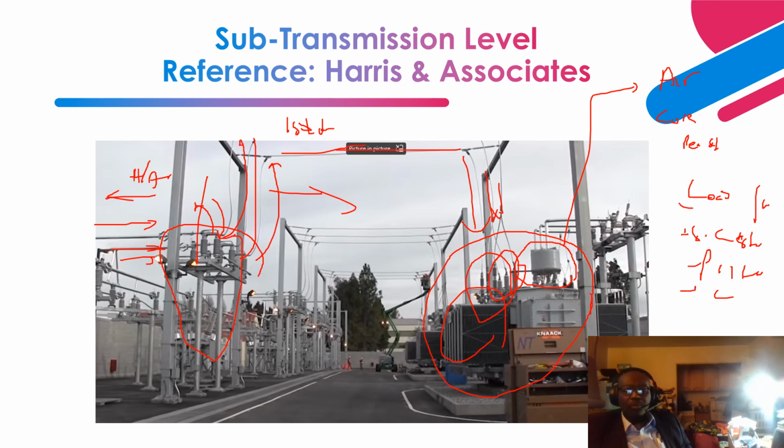Okay, so when they do the protective relay and the short circuit studies, they find out the available short circuit that is flowing from the utility source, coming from the previous slides that I showed you, where that circuit breaker interfaces, coming from the 69 kV source.